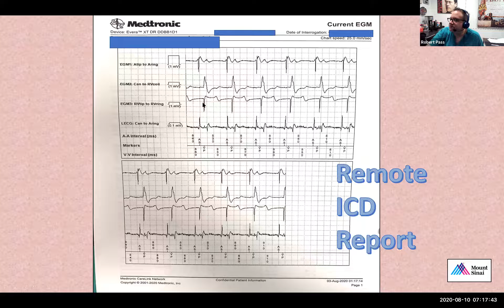If a box is 1 millivolt, then theoretically, this should be larger than that. So I'm not sure how this measurement was attained. And then this is the sensitivity that we've set. Here is the mode that the patient is on. So if somebody is looking at this remotely, or if you're on call and someone does a download and you have to look at it quickly, you can see how the patient is programmed.